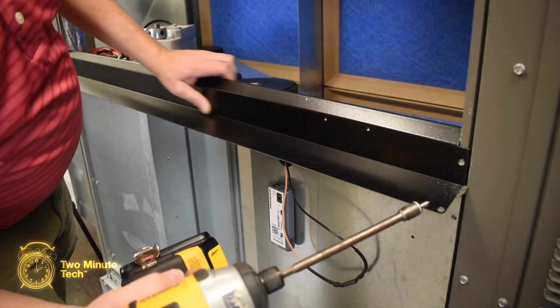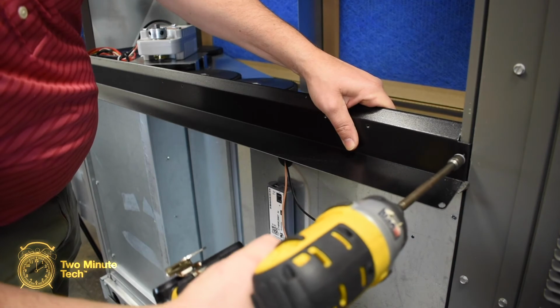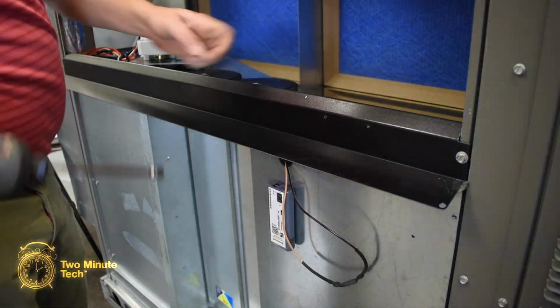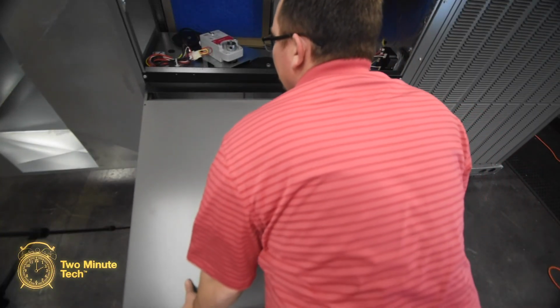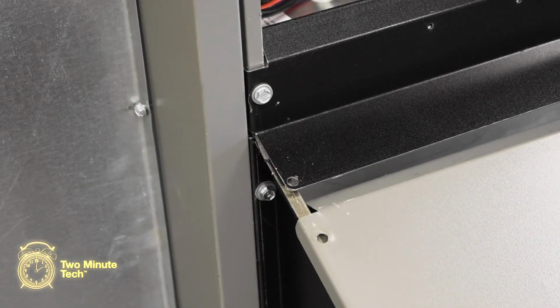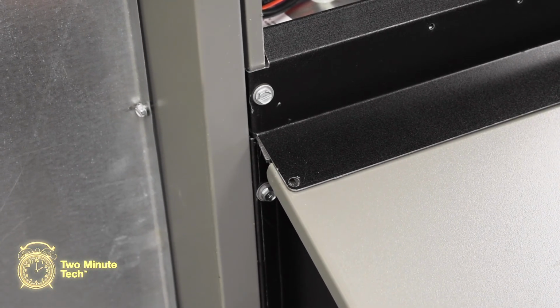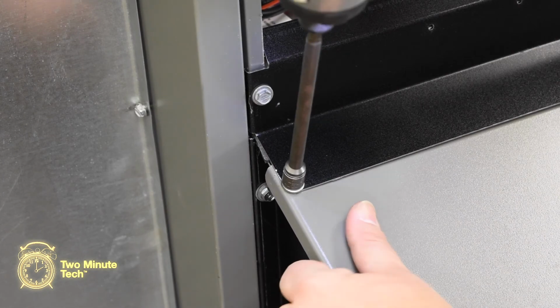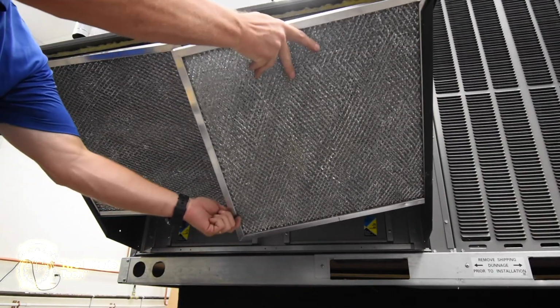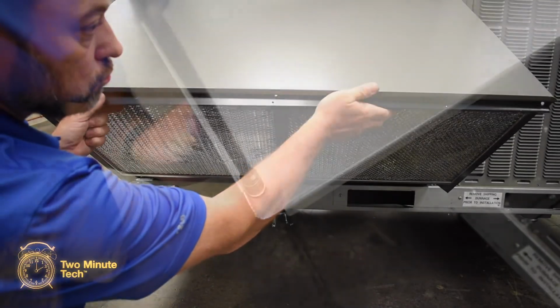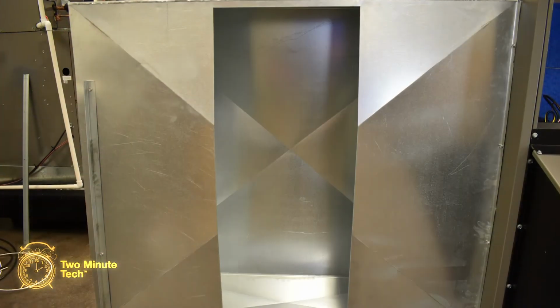Install the angled rain cap across the top of the economizer, securing with 1 screw on each side. Using the lower air filter access panel, previously removed, set it on top of the hood sides and slide it up under the rain cap. Secure with screws at the top edge only. Install the fresh air intake filters into the opening of the hood and attach the upper filter support rail to the bottom edge of the hood panel, securing with 3 screws.